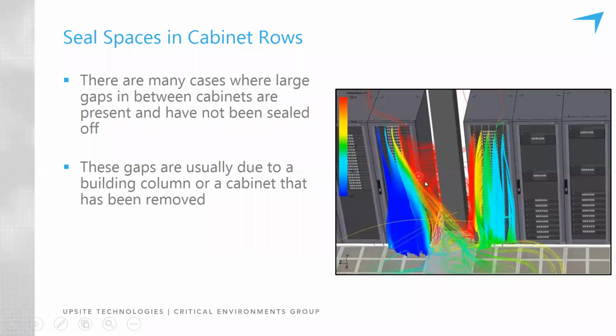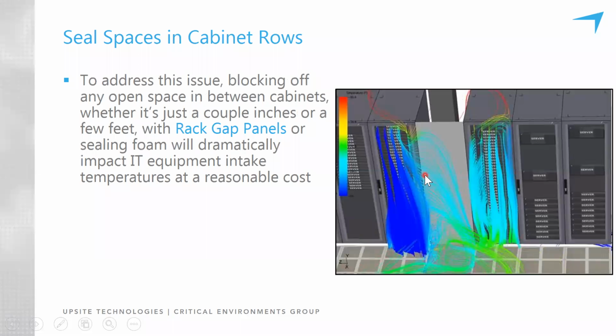So once this gap is sealed, the opening is blocked, of course, and now the exhaust air cannot flow through that space, and the conditioned air that's available in the cold aisle can now make it to the inlets of the IT equipment. And it's important to point out that in both the CFD models for the under rack openings and this in-row opening, there was no change in the amount of conditioned air supplied to the aisle or the temperature of the conditioned air before and after. These before and after images are purely the result of just blocking an opening.